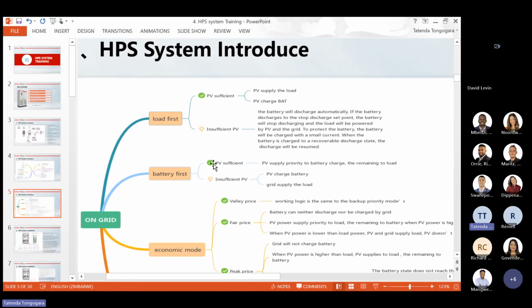Okay. In on-grid mode, we have load first, battery first, economic mode. So PV sufficient, PV supply the load, and PV charge the battery. When it's insufficient, then you discharge your battery. If the battery is insufficient, you can start your generator.